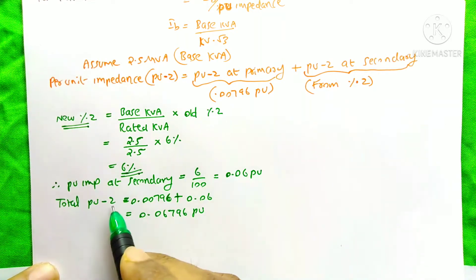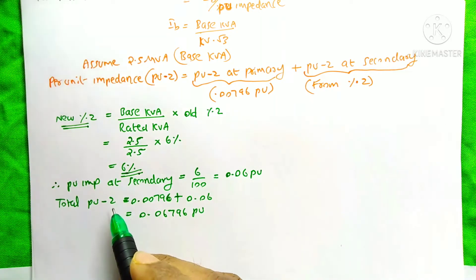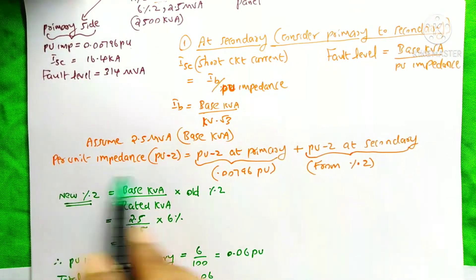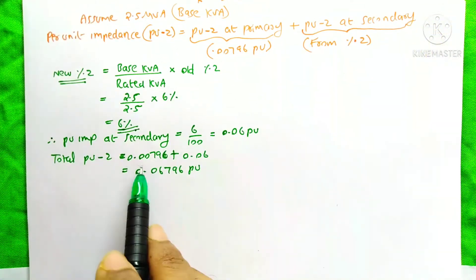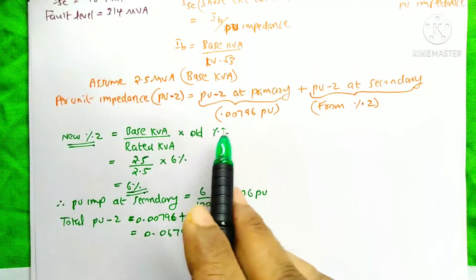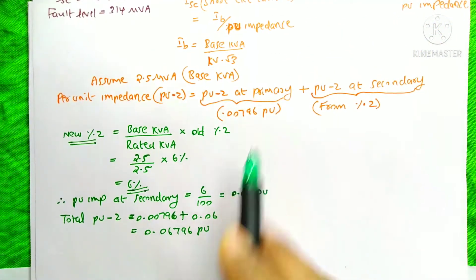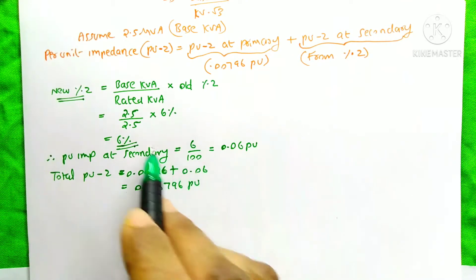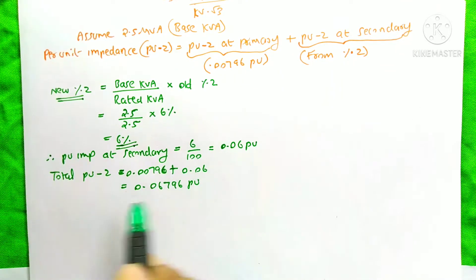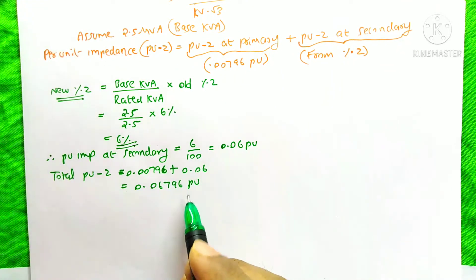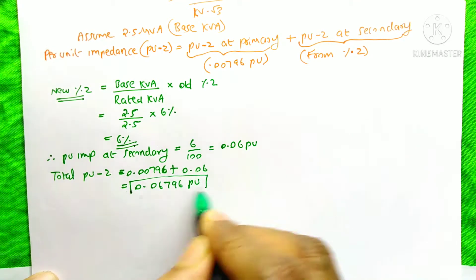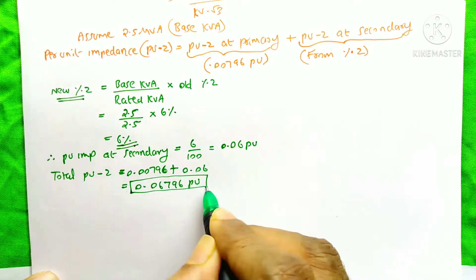The total per unit impedance is 0.00796 plus 0.06, which equals 0.06796 per unit impedance. This is the total per unit impedance at the secondary side.